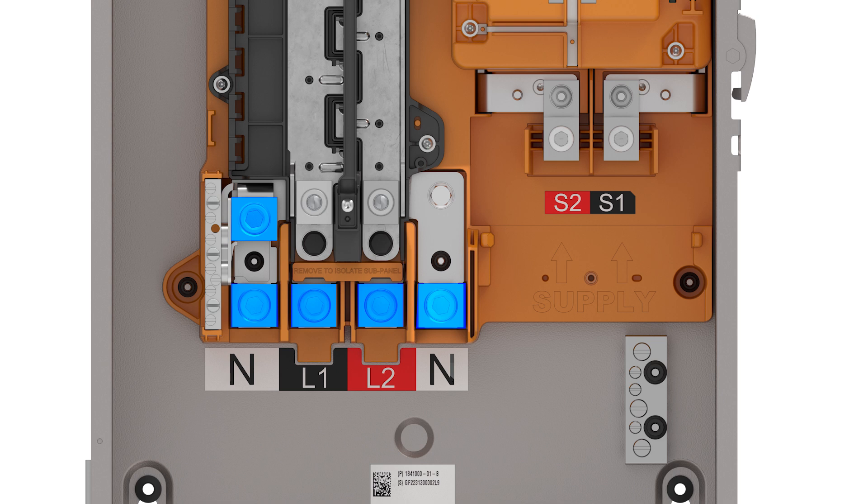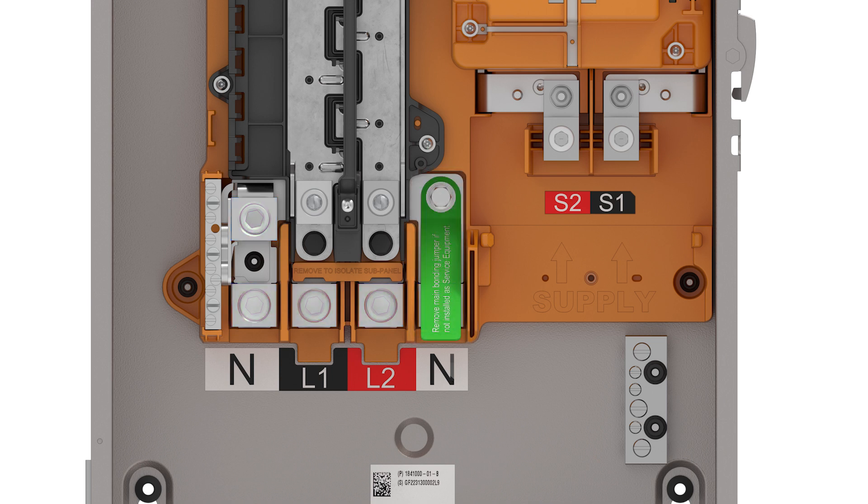Please note, neutrals are not allowed to be double lugged unless they are running in a parallel circuit as permitted by code.